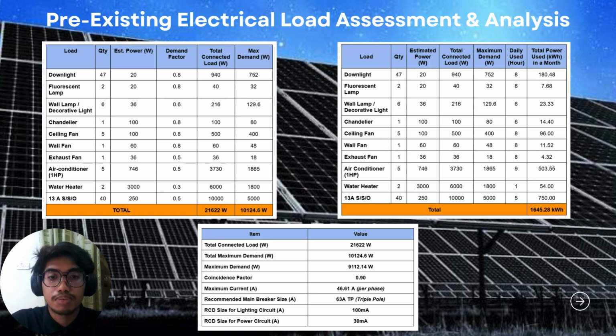Then the maximum current. Maximum current equals maximum demand divided by 230 volt times 0.85 power factor for the residential. That 230 volt is the standard nominal single phase voltage in Malaysia, and 0.85 is the power factor for the residential. For the size of the MCB, we get the overcurrent, which equals 1.25 times the maximum current. This follows the Suruhanjaya Tenaga requirement for a safety buffer, usually 125% or 1.25 for continuous or overcurrent protection.